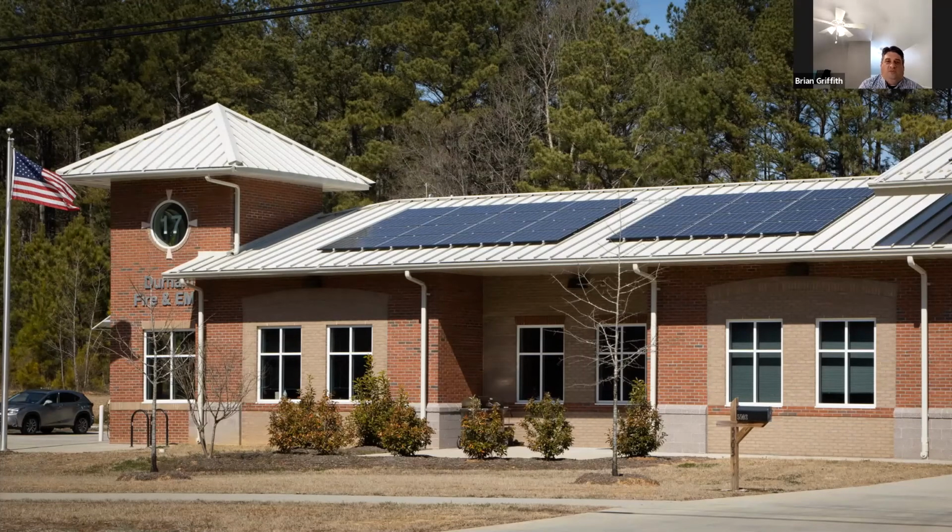One of the unique things that we had to take into account, because this is a fire station, was we have an emergency generator. So we have line power, we have emergency service generator, and we have solar power. And how do those three come together with our transfer switches to make sure that they have full power all the time? So we wound up being grid backed up. So the power went back to the grid before our generator. So everything worked directly off that transformer for the solar tied back there. And then we went to our transfer and generator system for the station.